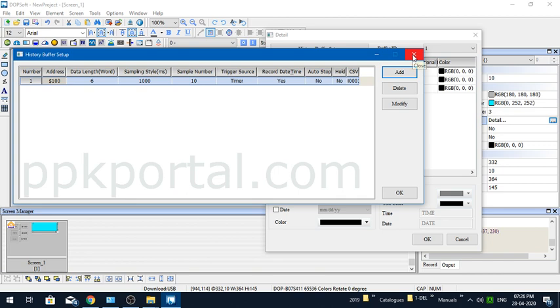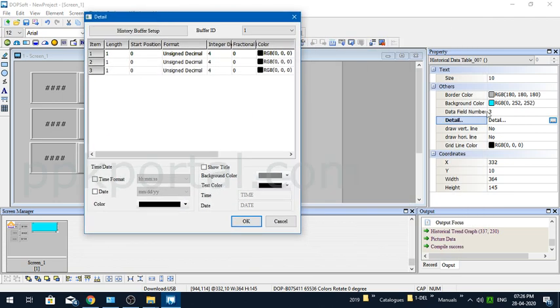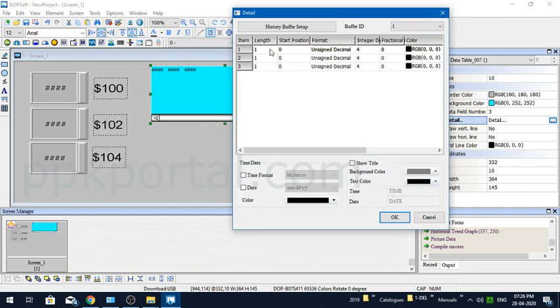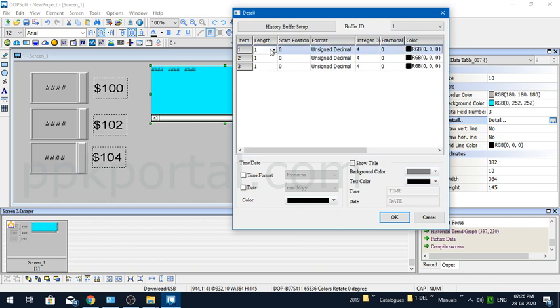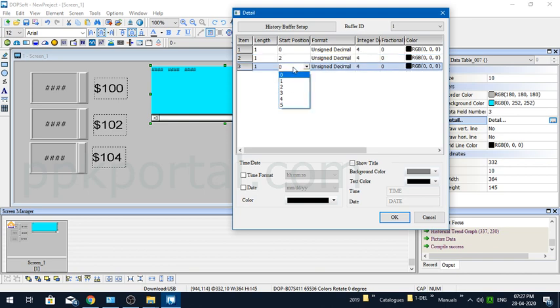Here you can see my buffer ID is one because I've already configured only one historical buffer. You can configure up to 12, I guess. In this story number one, you have three items already defined because I've pointed out that my data field number is three. Now here, the length—since it's word data, all the lengths remain as one. If it's floating data, you have to change it to two, or double word data you have to change it to two. This is the starting point. Remember, from $100 to $106, so $100 starting position is zero, $102 starting position obviously will be two, and $104 starting address is four.